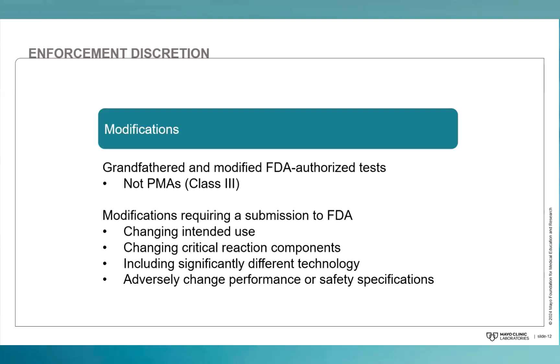If you're including significantly different technology, so if you're moving from one platform looking at targeted fluorescence to a multiplex bead fluorescence, for example, that would be considered a major modification. And then any change that would adversely affect the performance or safety specifications of a test would require submission to the FDA.